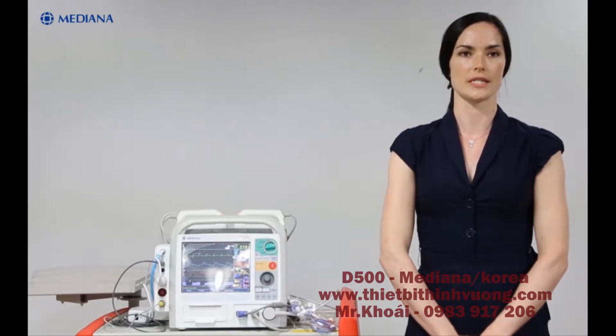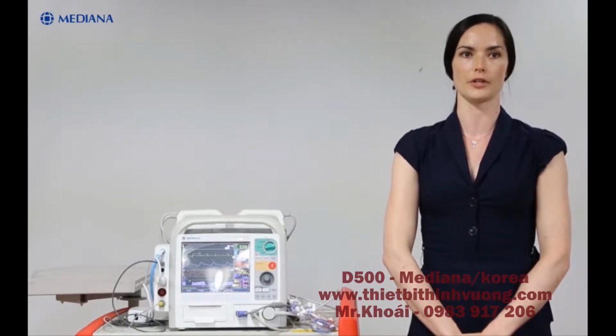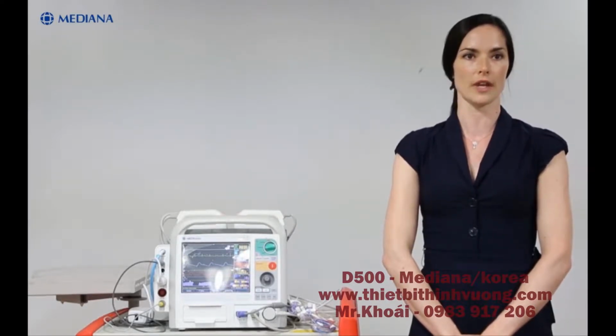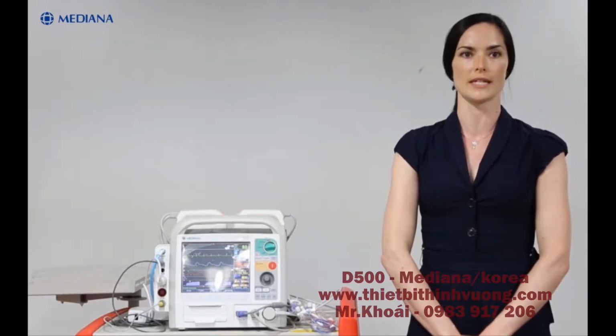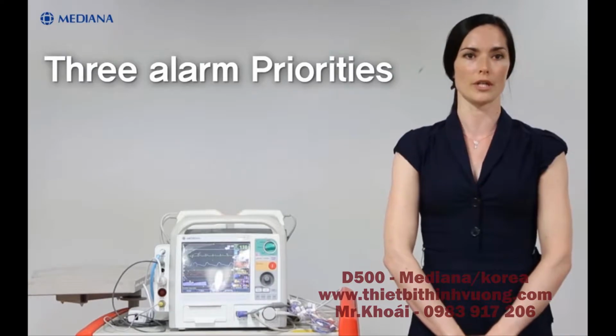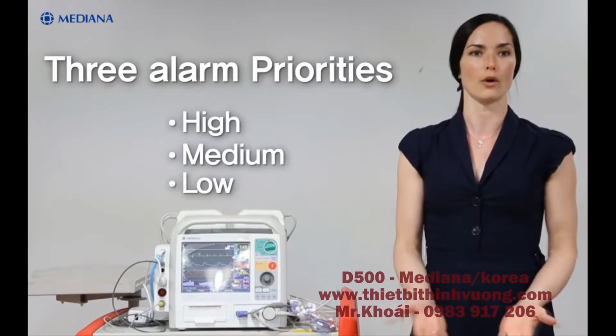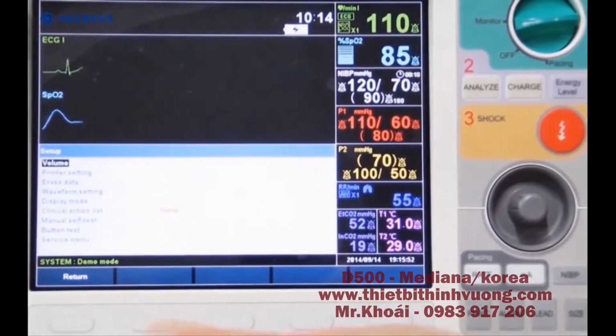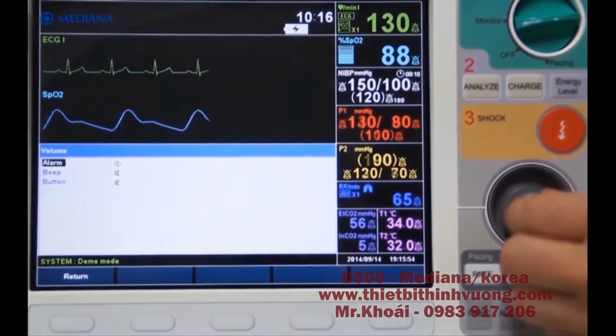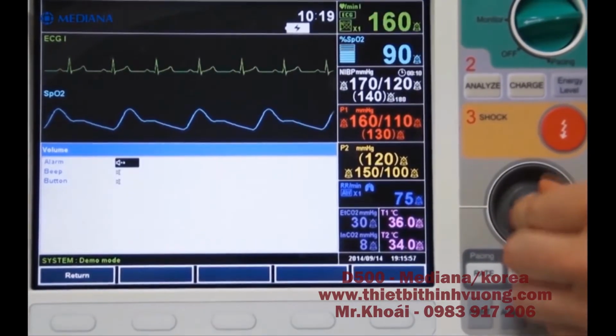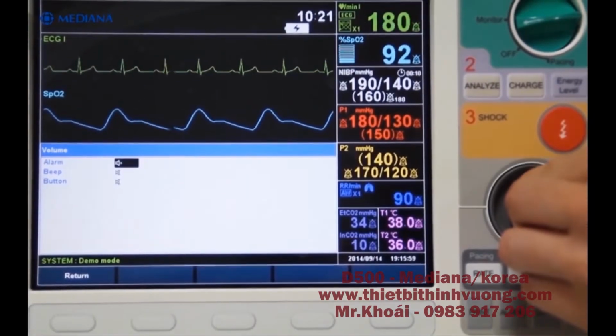When D500 detects certain conditions that require user attention, D500 enters an alarm state, and D500 response is indicated by audible alarm indication. Physiological alarms include identification of out-of-limit vital signs, and there are also technical alarms. And furthermore, there are 3 alarm priorities: high, medium, and low. To adjust volume, we can go into Setup menu and Volume menu. Then you can adjust the volume by the multifunction knob.